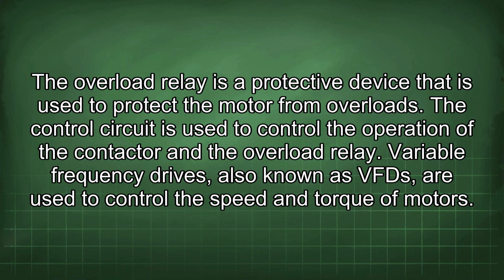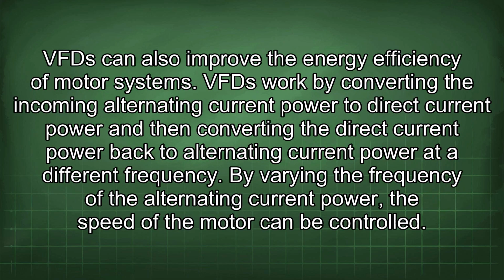Variable frequency drives, also known as VFD, are used to control the speed and torque of motors. VFD can also improve the energy efficiency of motor systems. VFD work by converting the incoming alternating current power to direct current power and then converting the direct current power back to alternating current power at a different frequency. By varying the frequency of the alternating current power, the speed of the motor can be controlled.